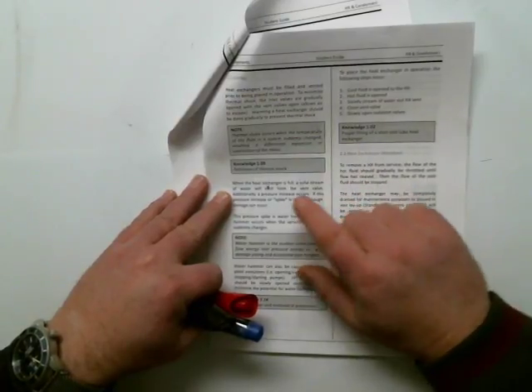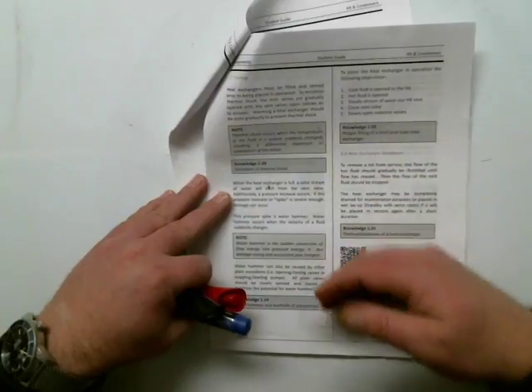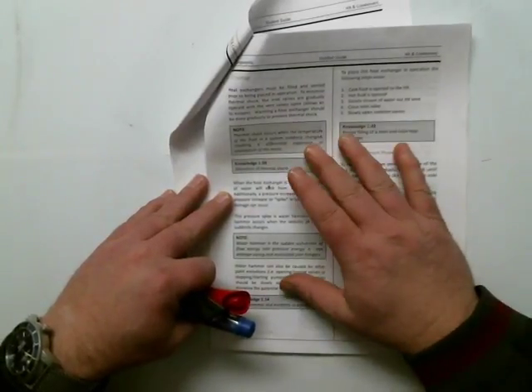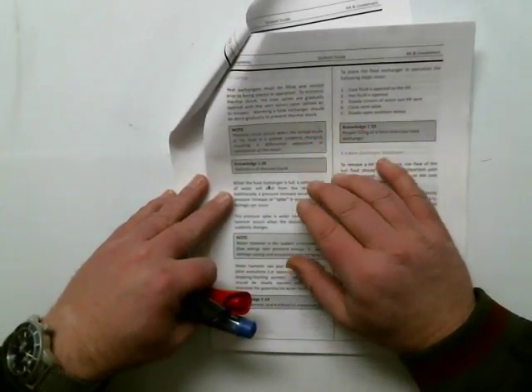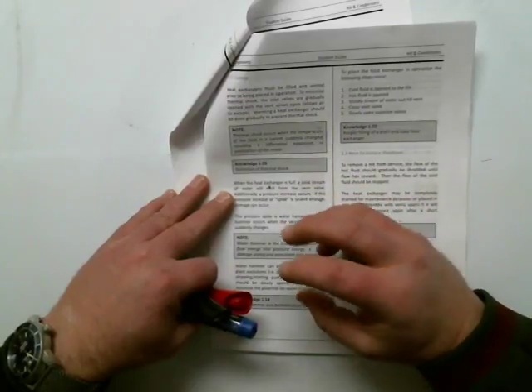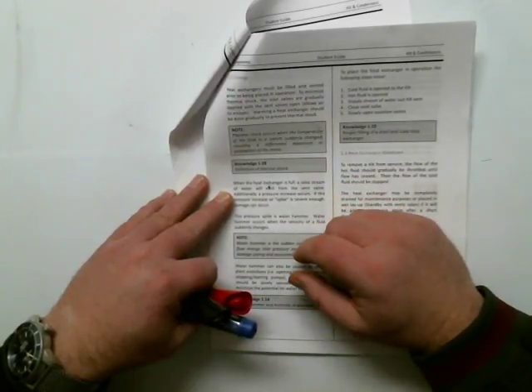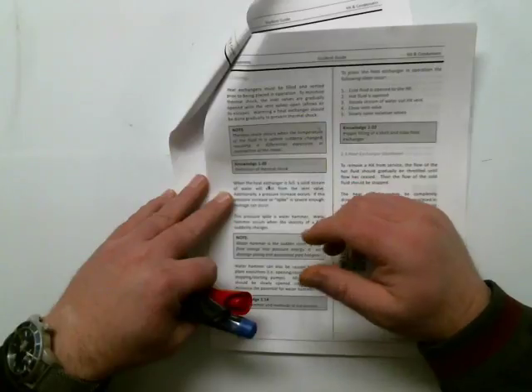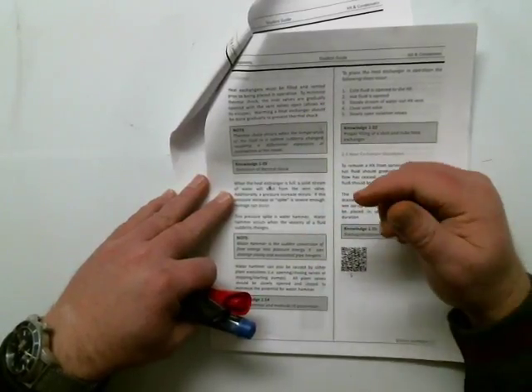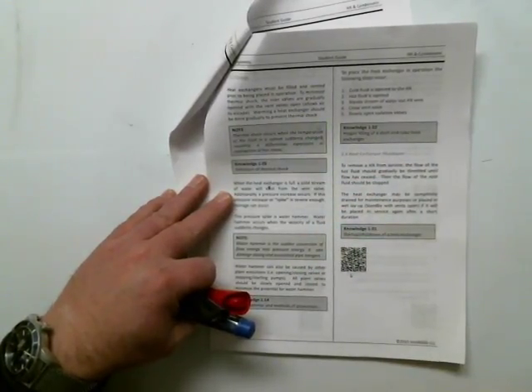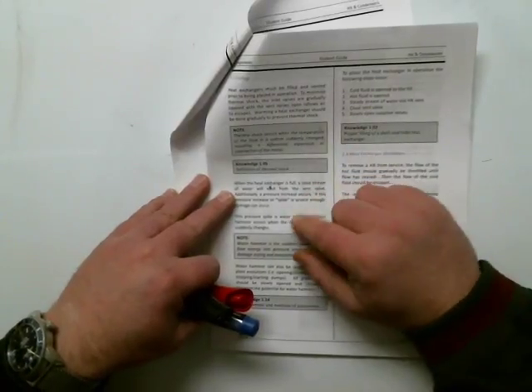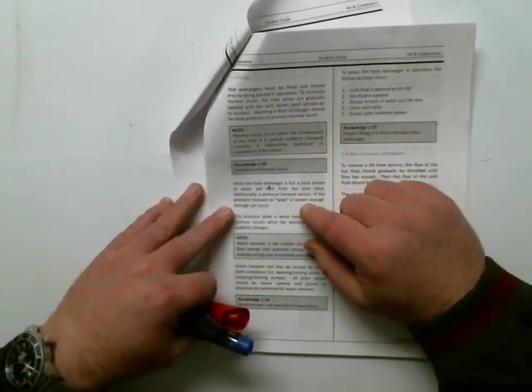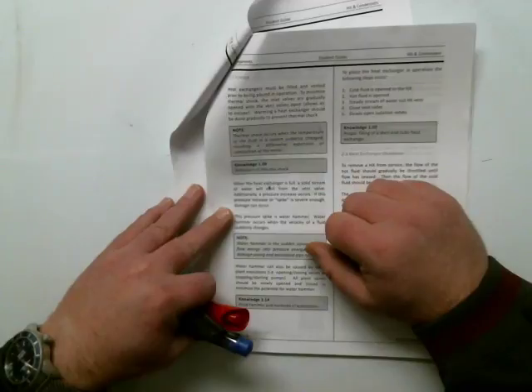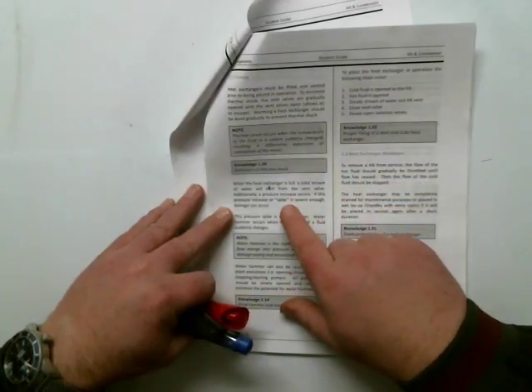And another thing we have to worry about, if you're reading this, is water hammer. Water hammer can occur, and the definition of water hammer is actually the conversion of the kinetic energy of our fluid to pressure energy. Because once again, excuse me, you can't create or destroy energy. You can only alter it in form. And what's happening is kinetic energy of the fluid is being converted to pressure energy, and this can cause a severe pressure spike.